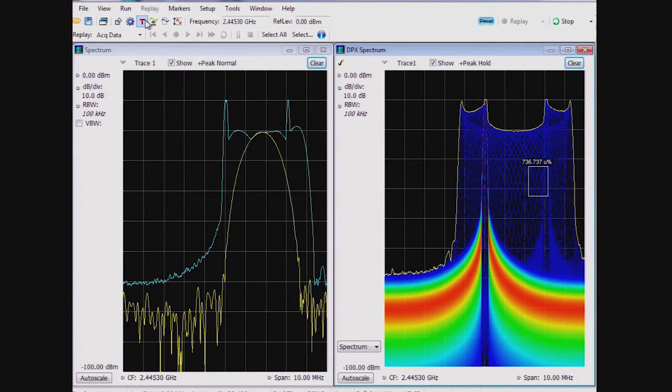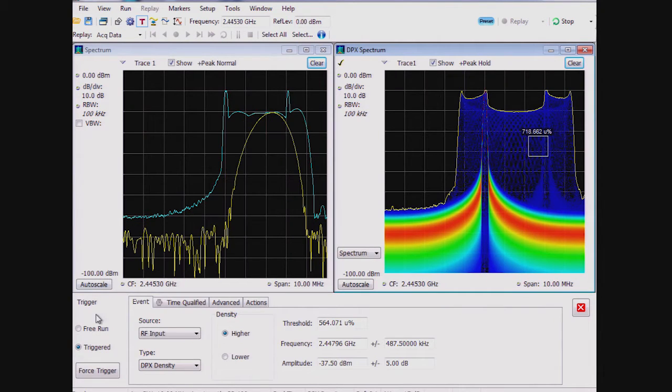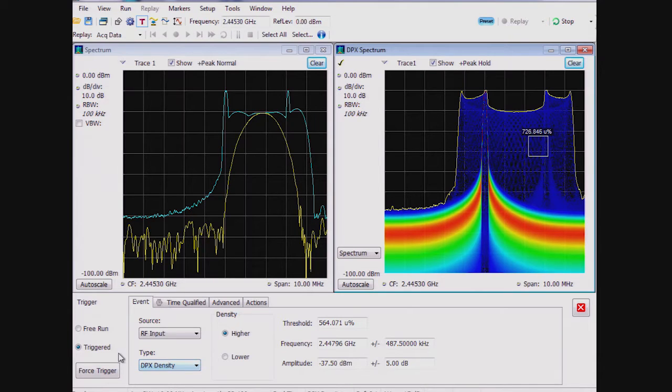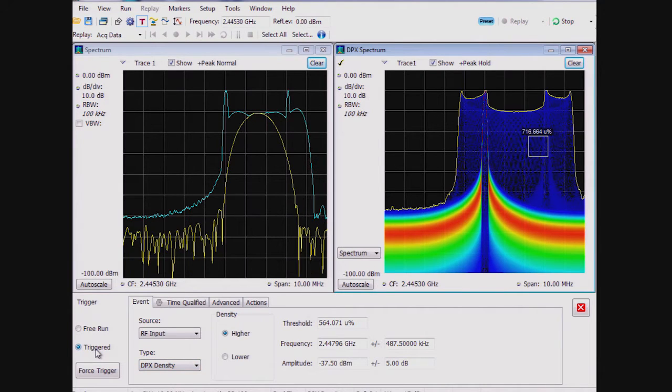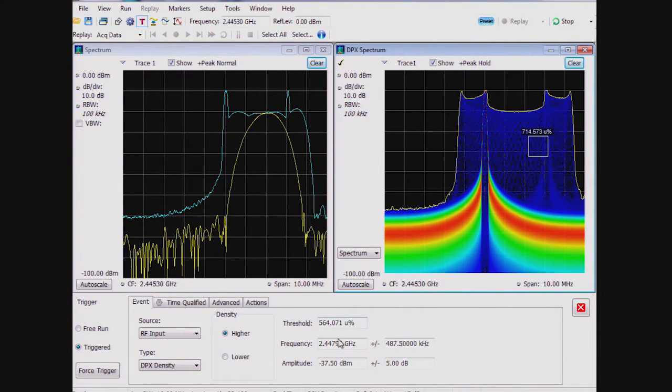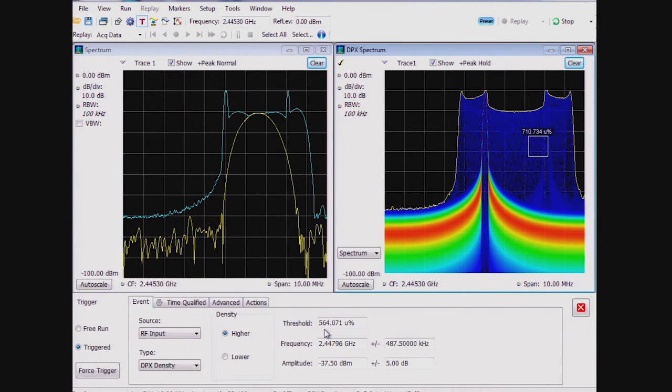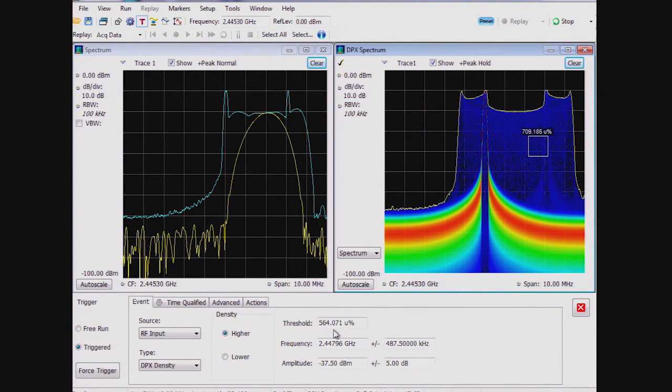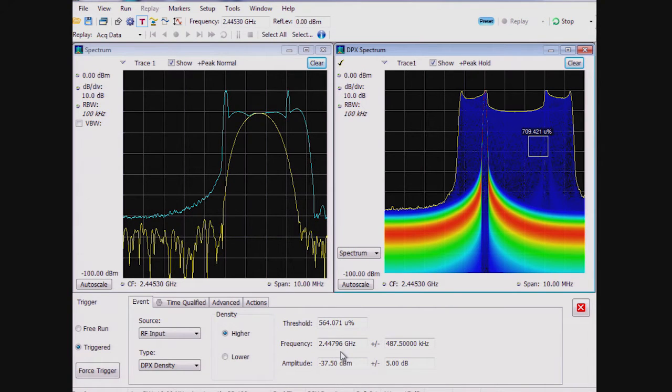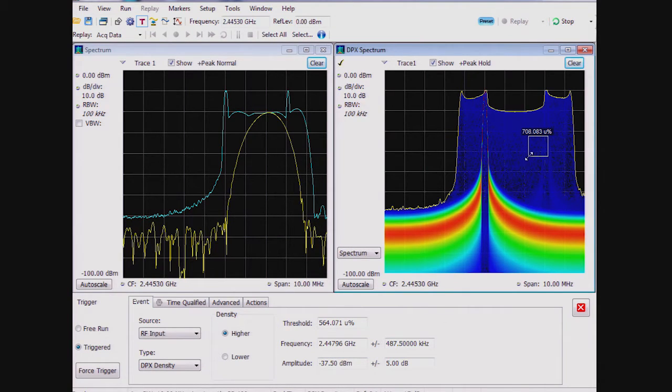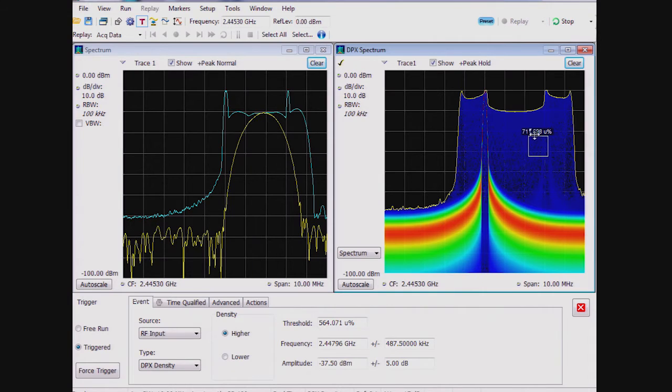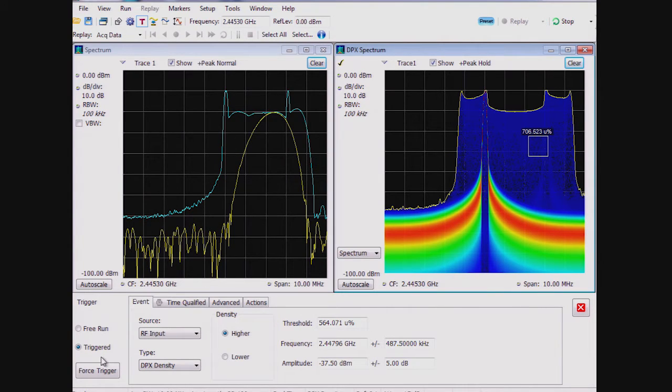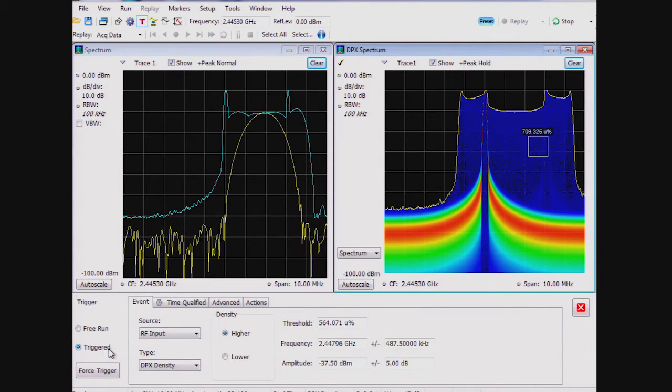First, the box was activated with a predetermined size and the signal density over time was measured. The signal density is different from that measured in other spectrum analyzers because it is measured over a period of time. Next, the trigger threshold is set to a level just below the measured signal density over time. Last but not least, the instrument's trigger was turned on to start the triggering.